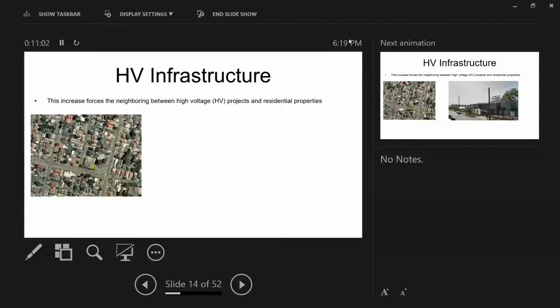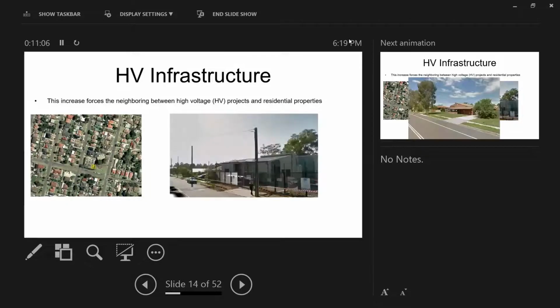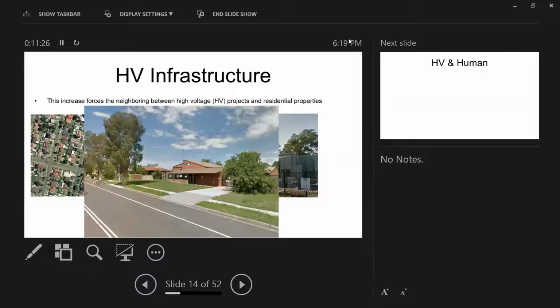Look, guys, at this. This is a real scenario based on a project that we've done before. That's a substation. That's high voltage infrastructure that, depending on the location of the substation, will attract lightning strikes and high voltage faults. This is another substation. Next to it, there's a house. That's a substation. That's a house. So people walking on the lawn in front of it, if the utility didn't do a proper design, God forbid, kids running or elderly people, they have a chance to get electrocuted by step voltage, which you will see, or by touching anything nearby.